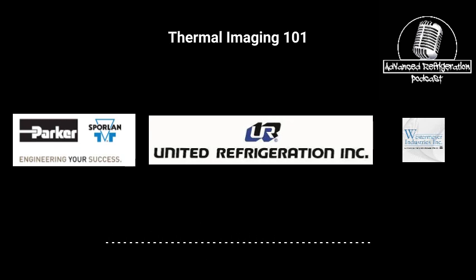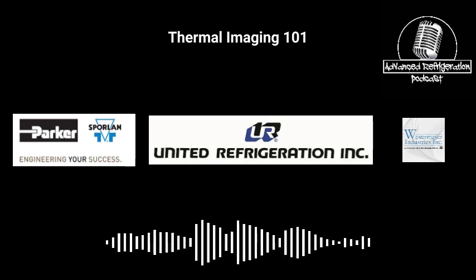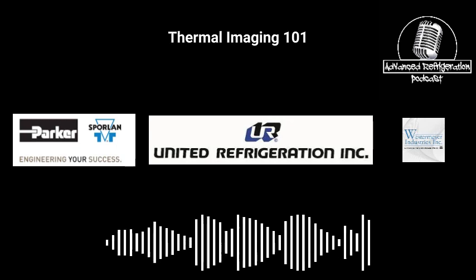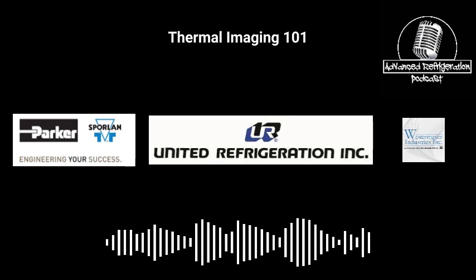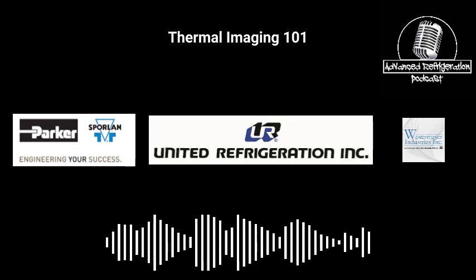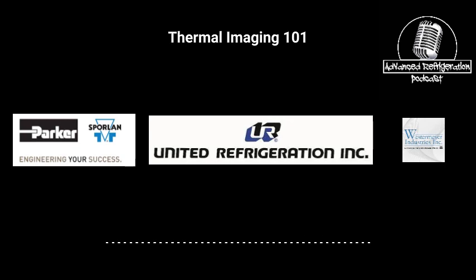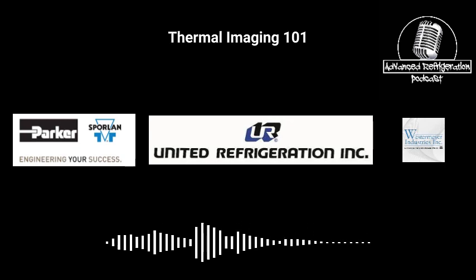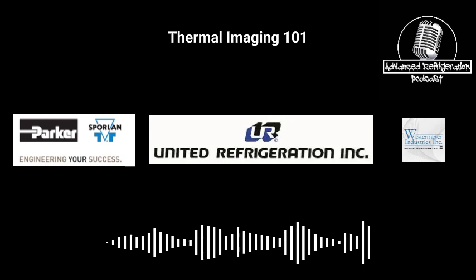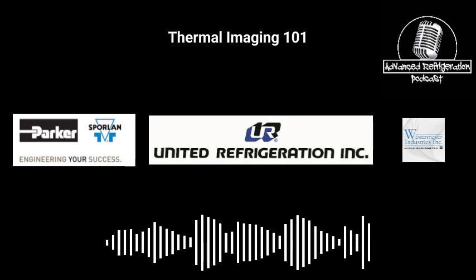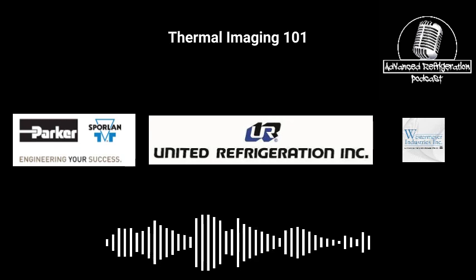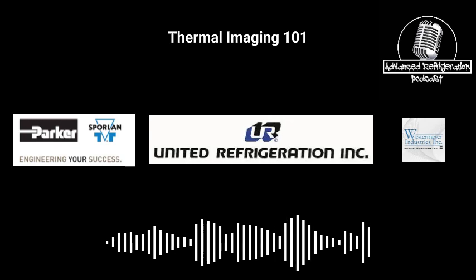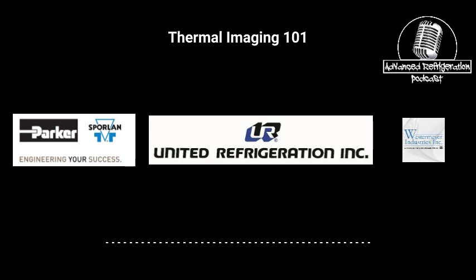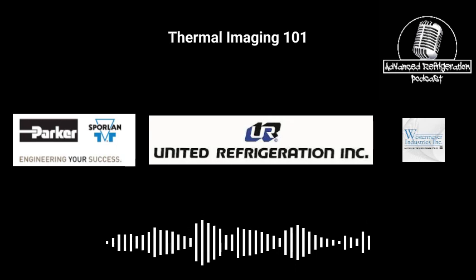And then my favorite thing to use it for is case troubleshooting, meaning multi-decks with product temp issues. You could scan the whole multi-deck, you could find a fan out. You could be scanning a 60 foot case and see one fan out, you see that one section, especially Hussmann cases, running warmer, or slightly warmer than the other sections. It'll lead you right to it. You'll see blue all the way across, and all of a sudden you'll see an orangish spot where it's slightly warmer, and you can go over there and check your airflow.